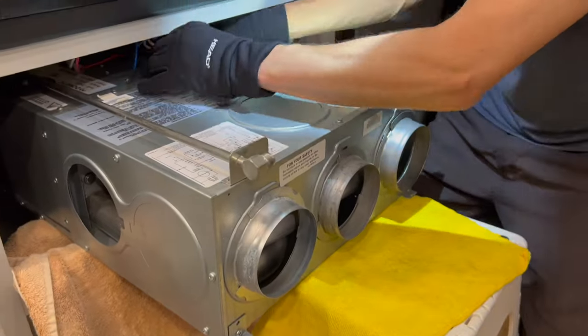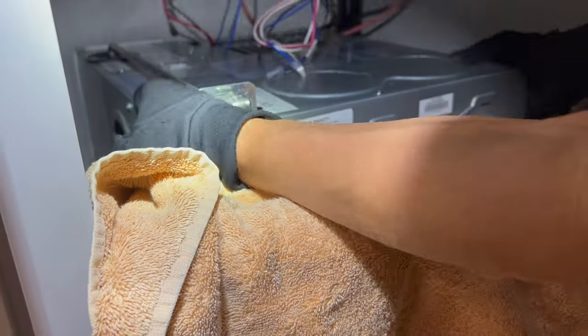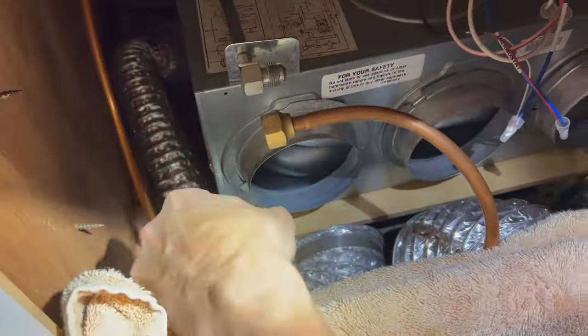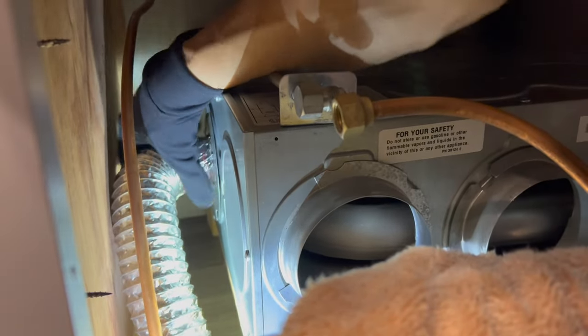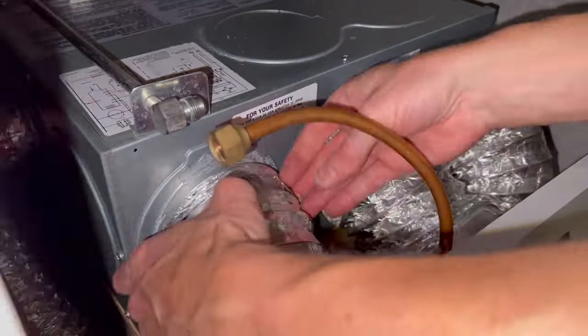Step 12: Re-install the furnace. With work gloves on, turn the furnace to the original position, lift it over any threshold, and put it back into the recessed area. Be careful not to kink any wires or hit the propane line. Re-attach the mounting screws to secure the furnace. Step 13: Re-attach electrical wiring using your pictures or labeling. Step 14: Re-attach ductwork in reverse order, making sure all ductwork is securely attached — my unit had a side duct as a manual screw metal plate and front ducts attached with clamps.